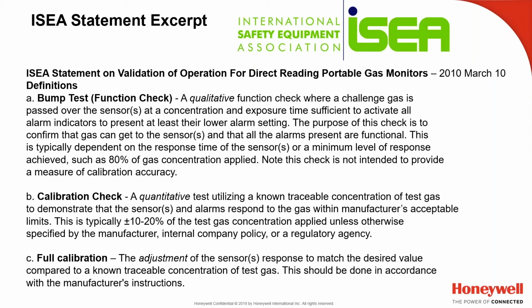And typically it's dependent upon the response time of the sensor or the minimum level of response achieved, such as 80% of the gas concentration. So if I apply 100 ppm CO, I might set the threshold that if it reaches at least 80, I'm going to give it a pass. Note the check is not intended to provide any measure of calibration accuracy. That's where calibration check comes in.